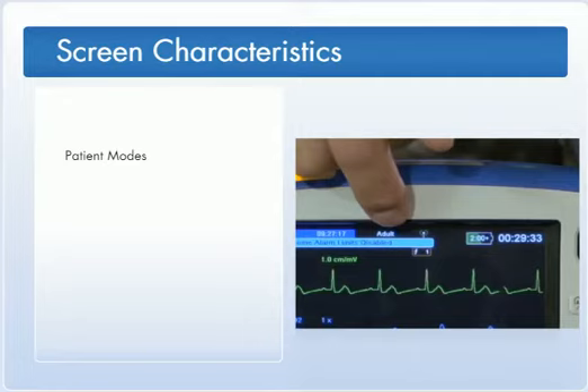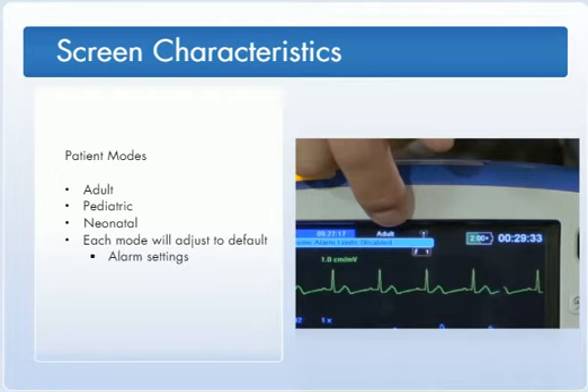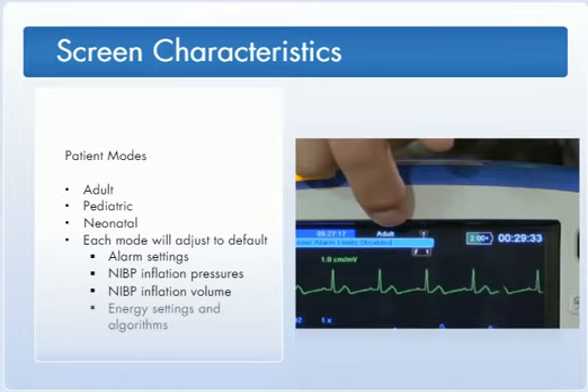The X-Series offers alarm settings for adult, pediatric, and neonatal modes. The latter is available only from Zoll. You can see the indicator at the top of the screen. Each mode will adjust to default alarm settings, NIBP inflation pressures, NIBP inflation volume, and initial energy settings, as well as mode-appropriate energy algorithms. Neonatal mode has not been approved for advisory defibrillation.